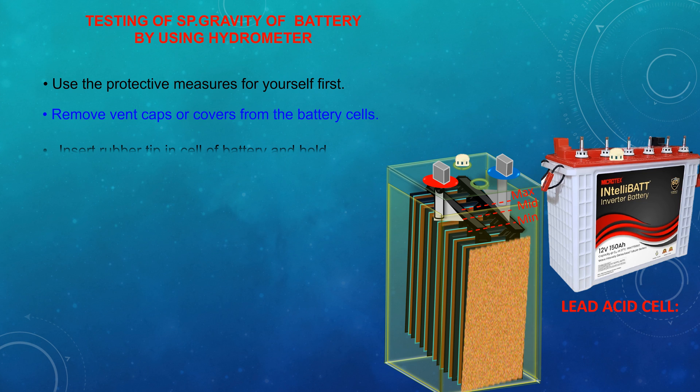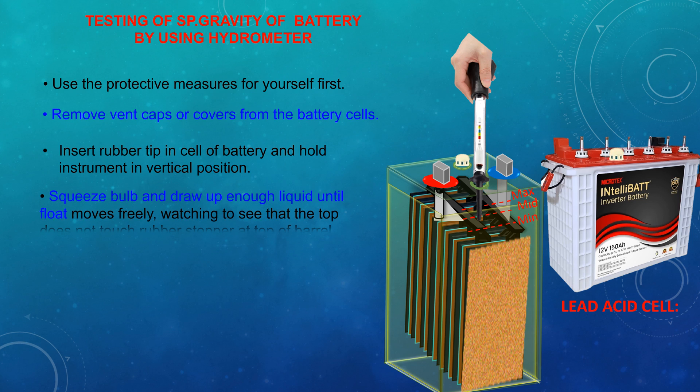Insert rubber tip in cell of battery and hold instrument in vertical position. Squeeze bulb and draw up enough liquid until the float moves freely, watching to see that the top does not touch rubber stopper at the top of the barrel.